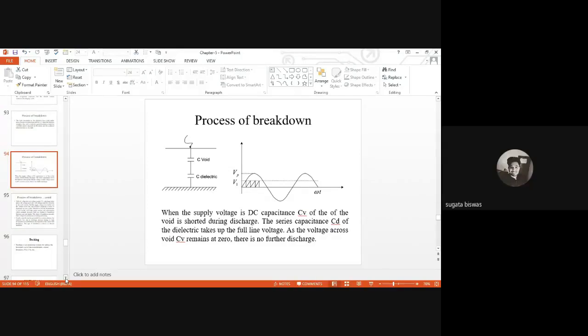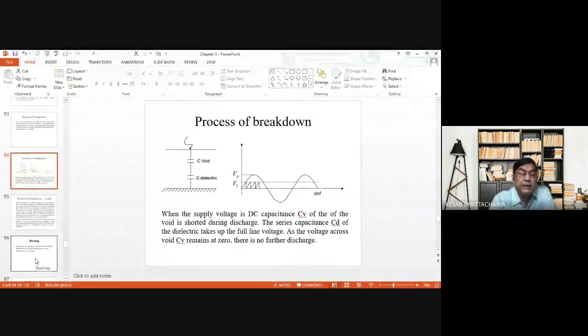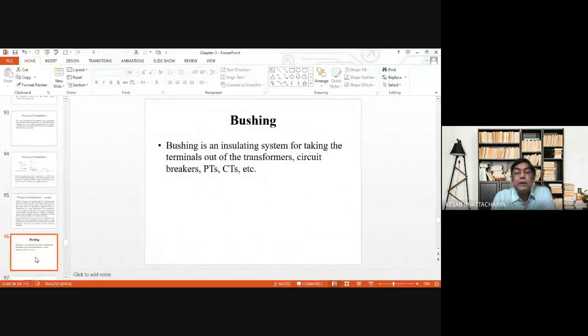Yes, sir. Okay. Next, let us discuss bushings. Now, bushing, you must have seen, is an insulator made of insulating material, looks like a pin type insulator or so. These bushings are used for taking the connections out or taking the connections into high voltage equipment like transformers, circuit breakers, potential transformers, current transformers, etc.